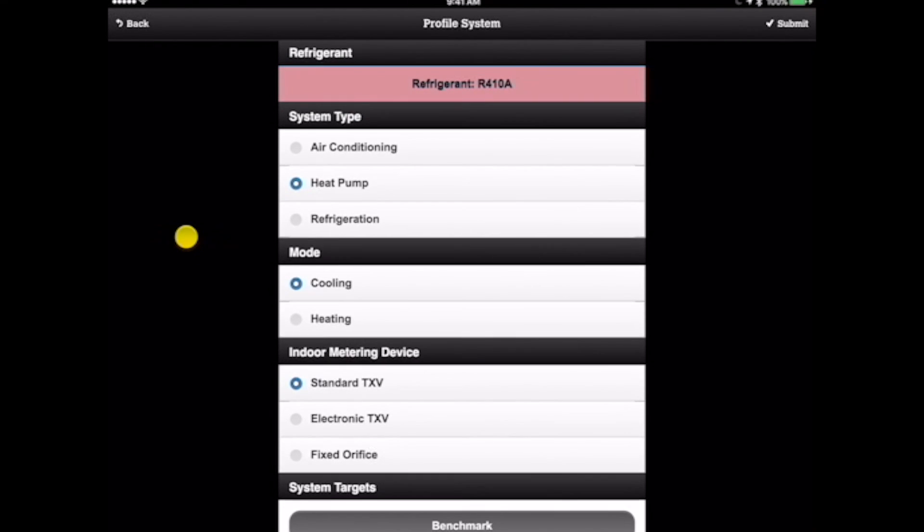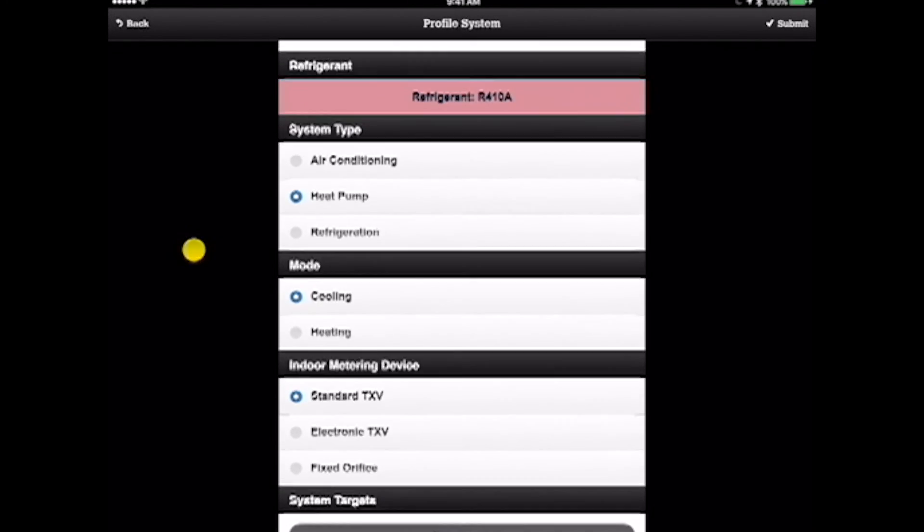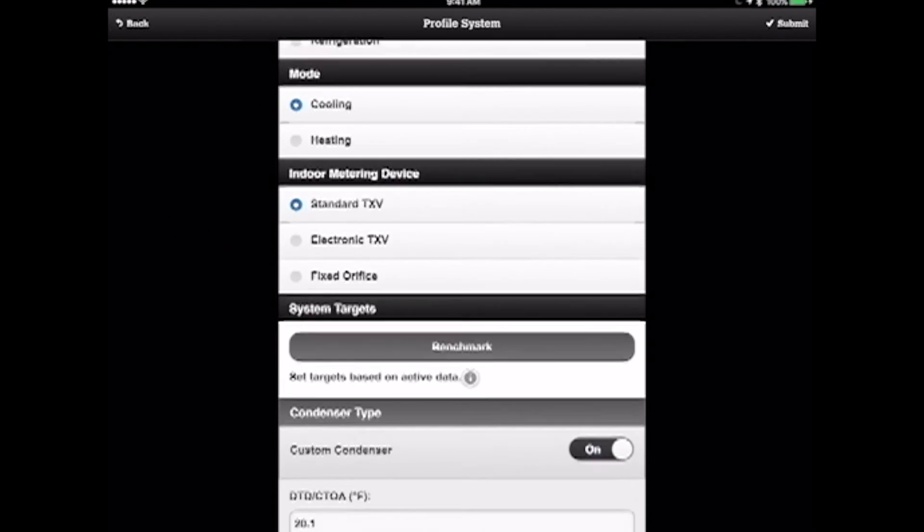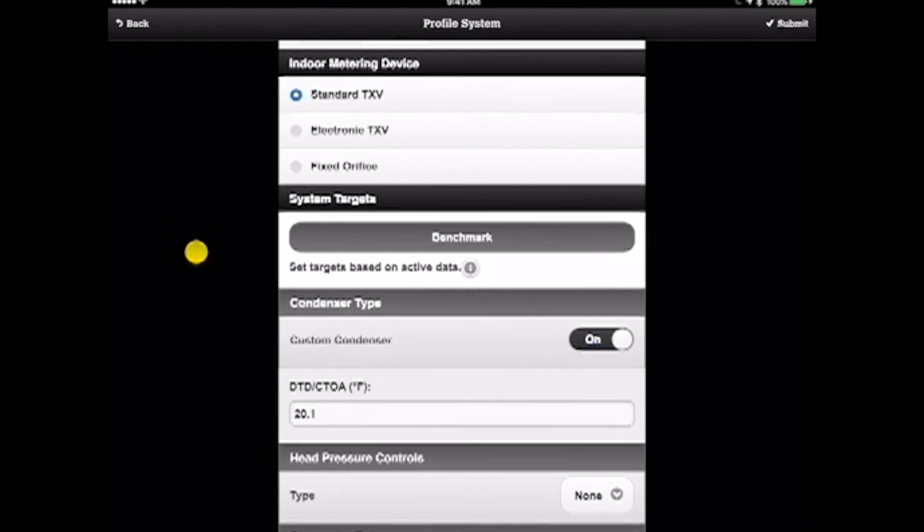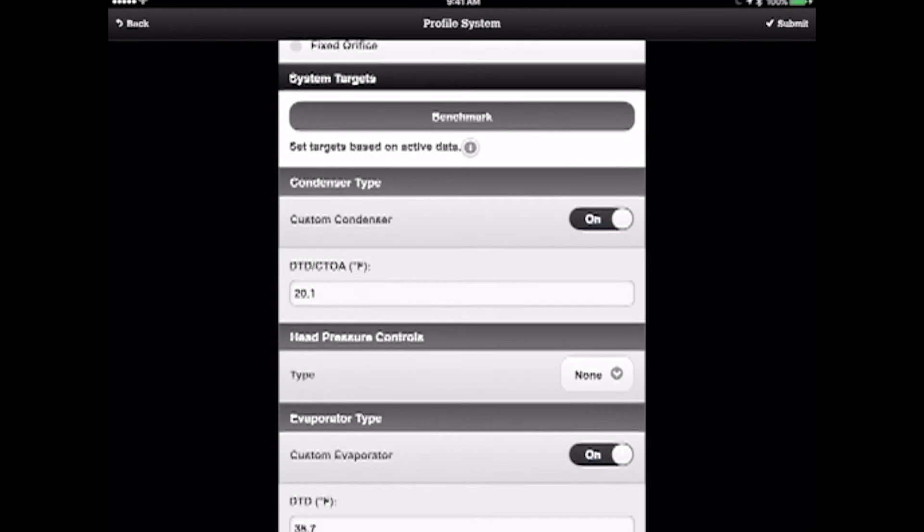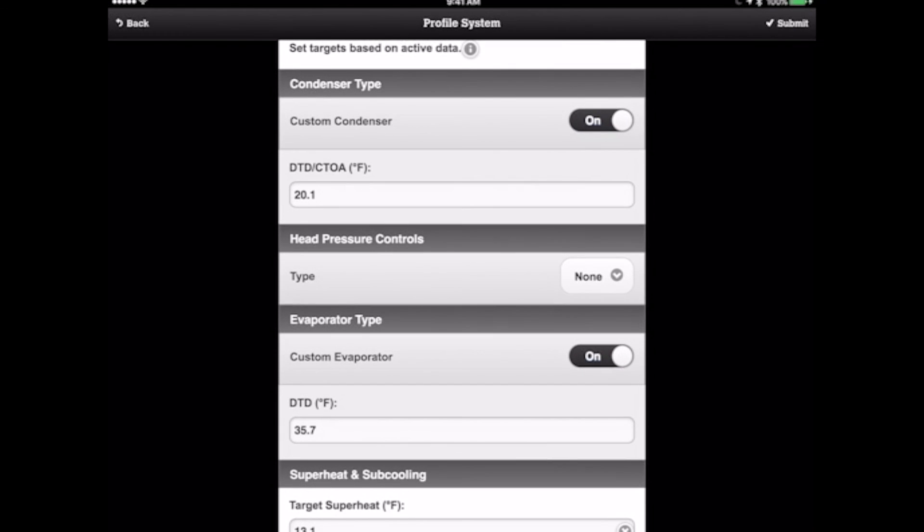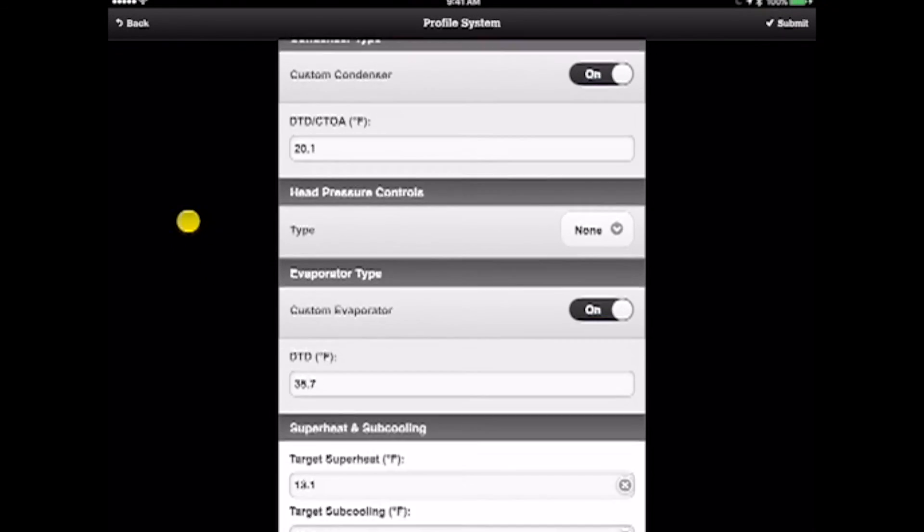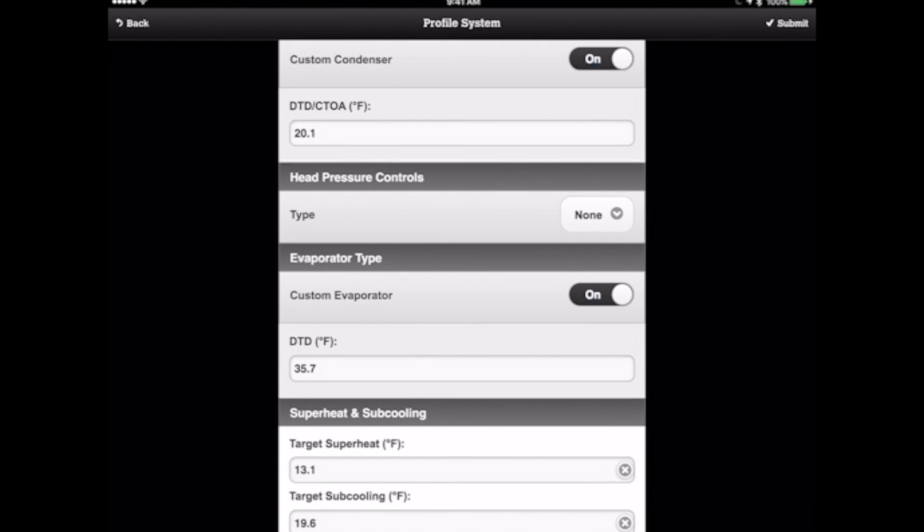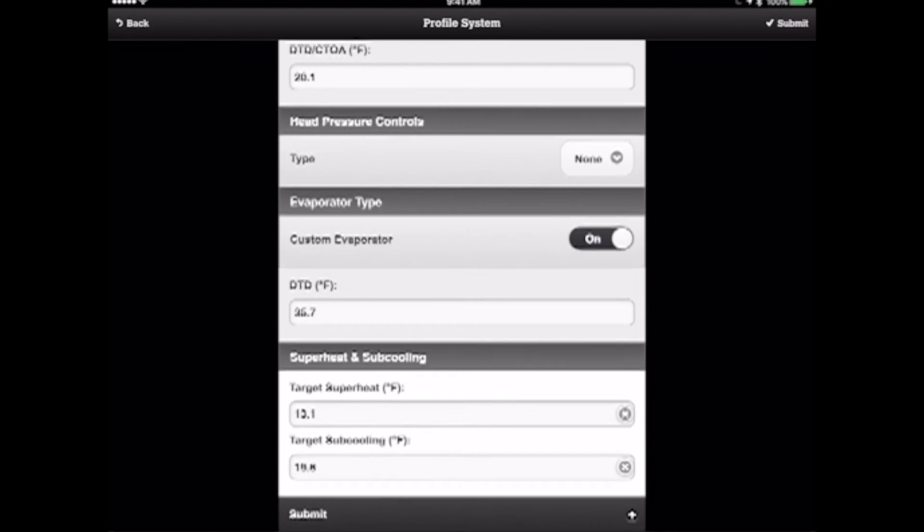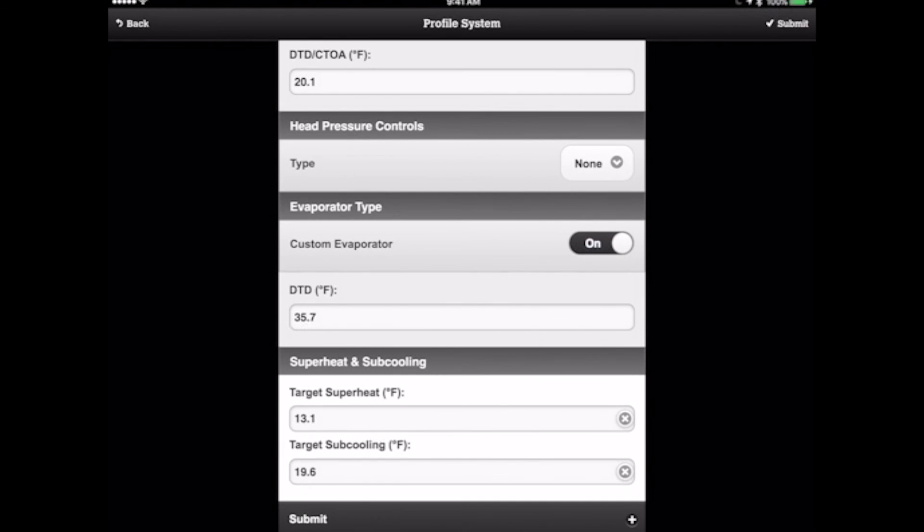Because they're going to have the exact profile that I used for this piece of equipment when I came out and commissioned it. So they're going to know right away that this is a heat pump in the cooling mode with a standard TXV. It's going to have a design temperature difference of 20.1 degrees hotter than the outdoor air, and the evaporator is 35.7 degrees colder than the return air. I left it with a target superheat of 13 and a target subcooling of 19.6.